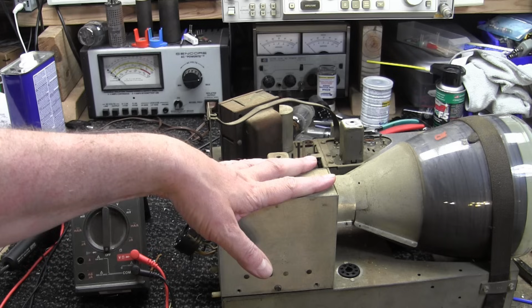What does that do? Well, it's a power transformer with a 1-to-1 ratio. You put 120 volts in, you get 120 volts out, but it's electrically isolated, meaning if you take an oscilloscope that is grounded and clip it to this, you're not going to have any problems. If it's a hot chassis and you've got it plugged right into an outlet, depending on which way you orient the plug, you could very well have this connected to the hot side of the AC line, and if you clip your grounded scope lead onto it, you're essentially shorting things out. You're going to blow a circuit breaker or blow a fuse.